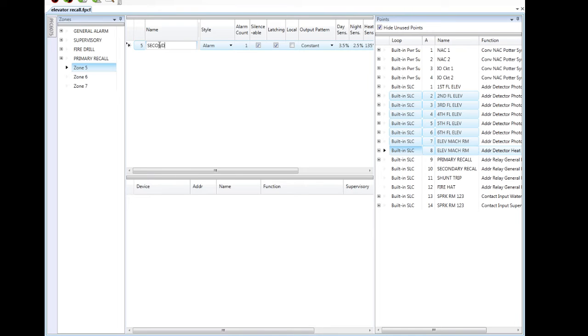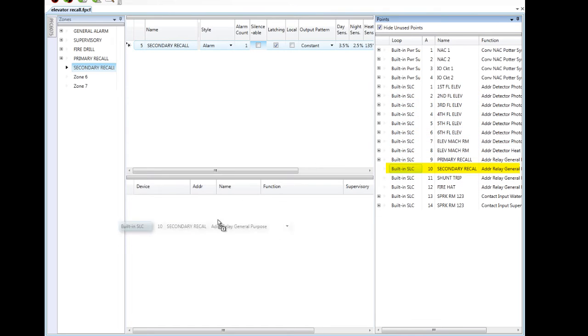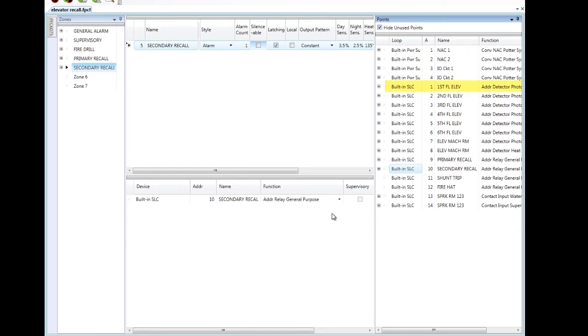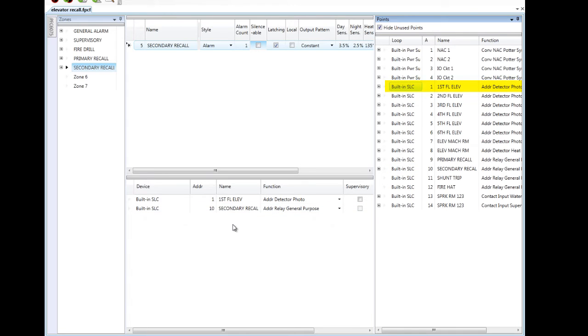My next zone I'm going to label secondary recall, also sometimes seen as alternate recall. Again, I'm going to make this zone non-silenceable. The output in this zone is going to be the secondary recall relay, so I'm going to drag that in there. What's going to trigger the secondary recall is going to be the first floor elevator lobby smoke. In the event that this smoke is active, I'd like to recall the elevators to the secondary floor of egress. So that's secondary recall.